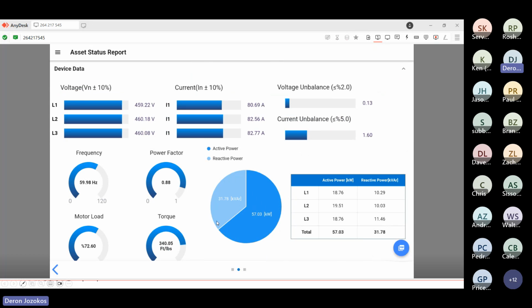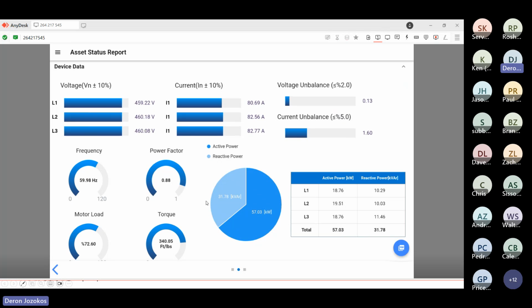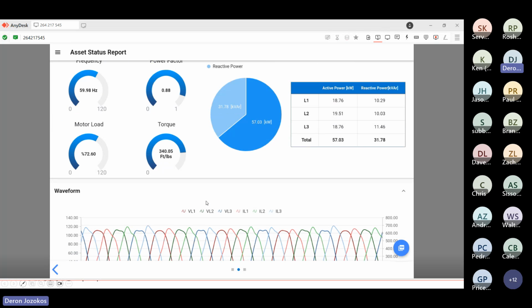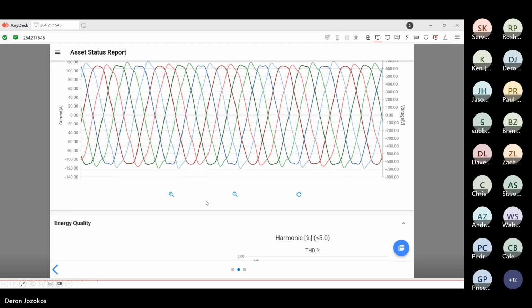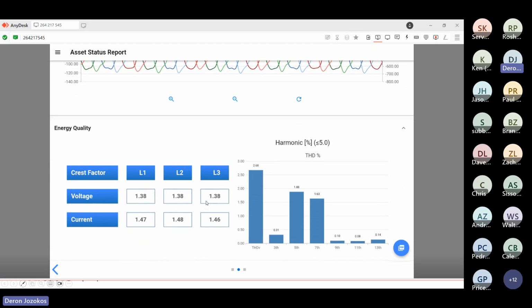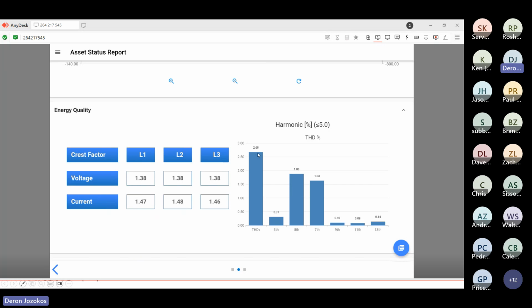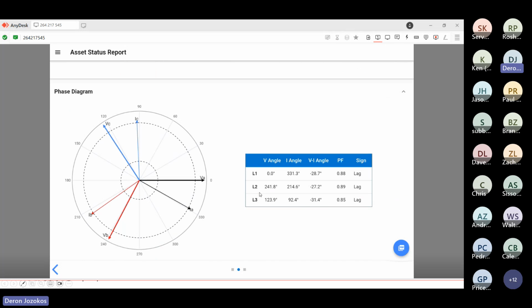That's page 1. On the second page, we get all of your electrical parameters, but we also have now added your waveforms, voltage and current. You have your harmonic levels, THD reported, so it's 2.6. That's actually a little bit high. Crest factor on the voltage and current, and the phase diagram. So when you initiate a test, it shows you this phase diagram, this vector plot, and will basically tell you if you set it up wrong, and all of this information as well.